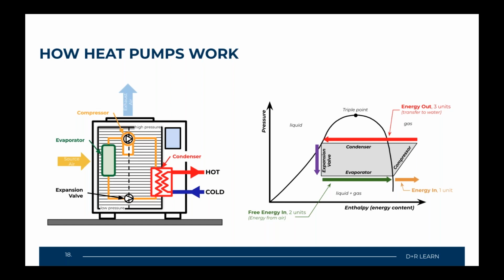Let's go through the vapor compression cycle quickly, the way a heat pump traditionally works, without the cooling factor involved. You have your evaporator system, your outdoor unit sitting outside, responsible for picking up the heat that will be delivered to your condensing unit, your water tank, or heat exchanger, where your unit creates hot water. So your evaporator pulls in heat energy, and in this case, with an air source water heater, it's pulling air and drawing heat from the air outside in order to make hot water.